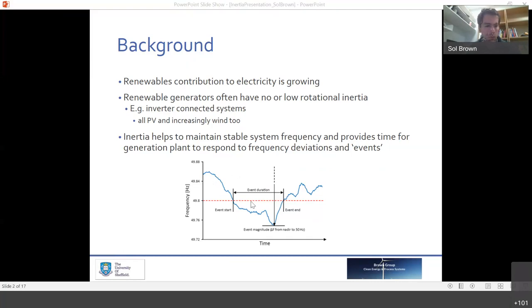And it helps generally maintain a stable frequency on the network. So when you're looking at events, where you have a sudden rapid power imbalance on our system, you have a frequency excursion a bit like this one. Your frequency will change with time, as it always does. It will fluctuate with the small imbalances on the system, and if a large imbalance occurs, then you'll hit the boundary within which you want your frequency to exist. And once you've moved out of that region, in the case of this figure downwards, you'll have a frequency event which you will have to respond to as a system operator. So that will mean deployment of additional power to bring yourself back up within the frequency bounds and minimize the imbalance.